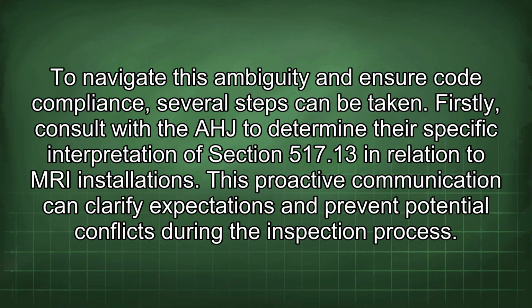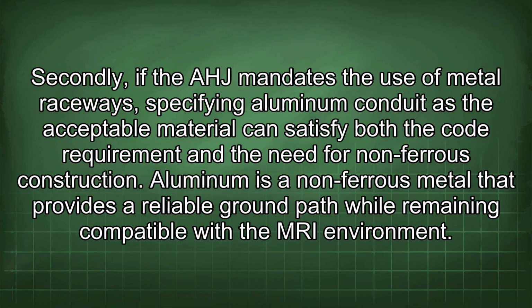To navigate this ambiguity and ensure code compliance, several steps can be taken. Firstly, consult with the AHJ to determine their specific interpretation of Section 517.13 in relation to MRI installations. This proactive communication can clarify expectations and prevent potential conflicts during the inspection process. Secondly, if the AHJ mandates the use of metal raceways, specifying aluminum conduit as the acceptable material can satisfy both the code requirement and the need for non-ferrous construction. Aluminum is a non-ferrous metal that provides a reliable ground path while remaining compatible with the MRI environment.